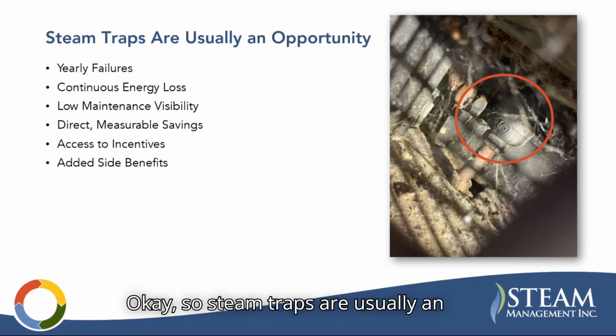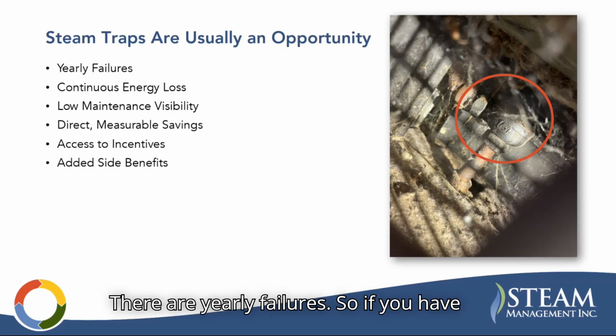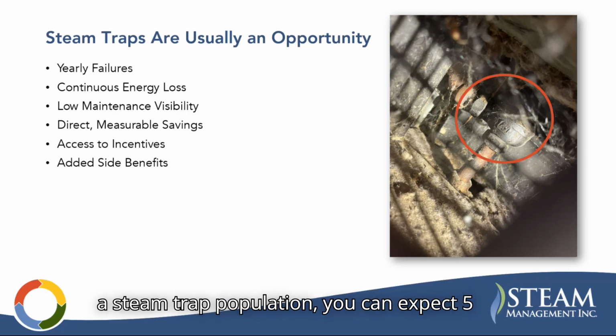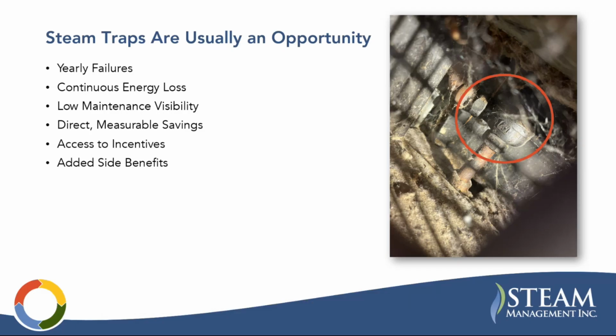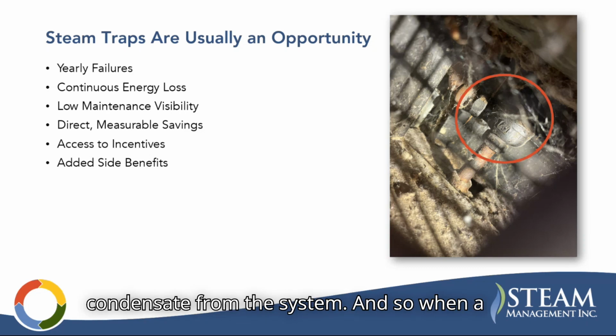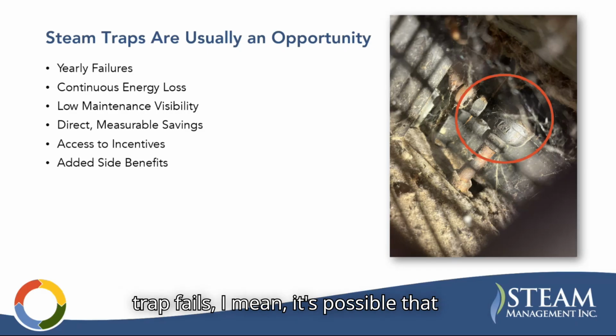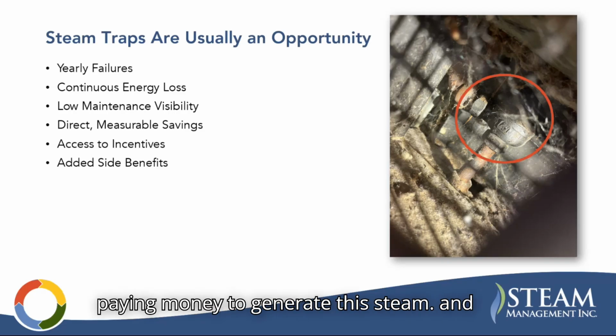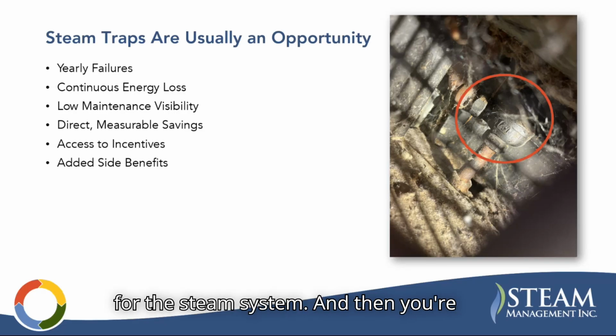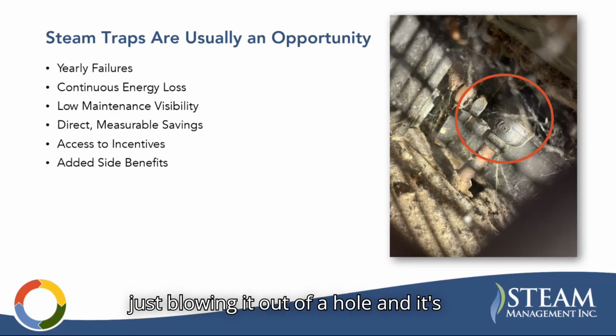Okay, so steam traps are usually an opportunity. I want to make that clear. If there are yearly failures, so if you have a steam trap population, you can expect 5 to 10% of those traps to fail every year. Traps are designed to fail open, so that they will still reject the condensate from the system. It's possible that they fail closed, but 90% of the time they're failing open. And then you basically have a hole that is constantly blowing steam. You're paying money to generate this steam and to treat this water for the boiler system, for the steam system, and then you're just blowing it out of a hole and it's escaping through the vent in your condensate collection tank. So it's a total waste.